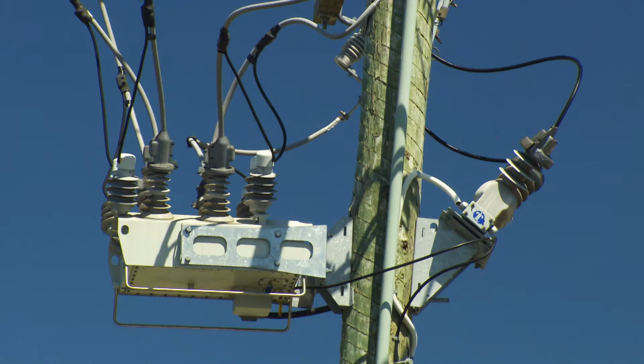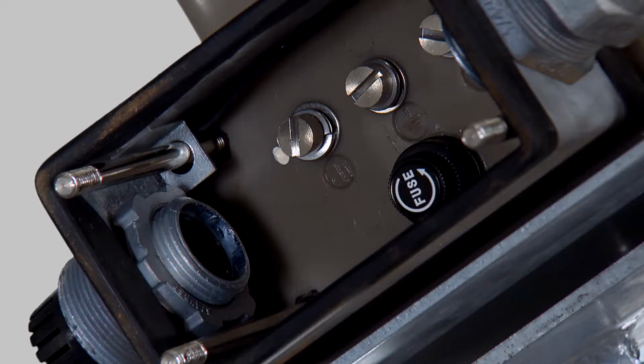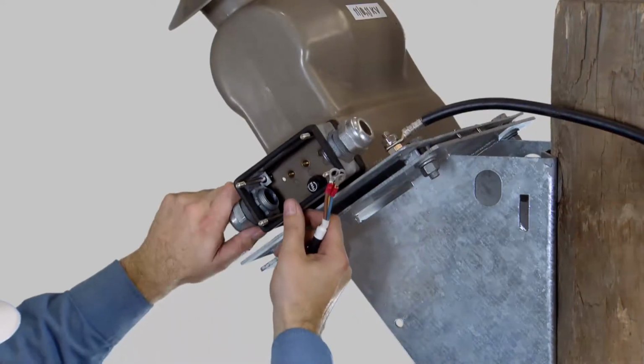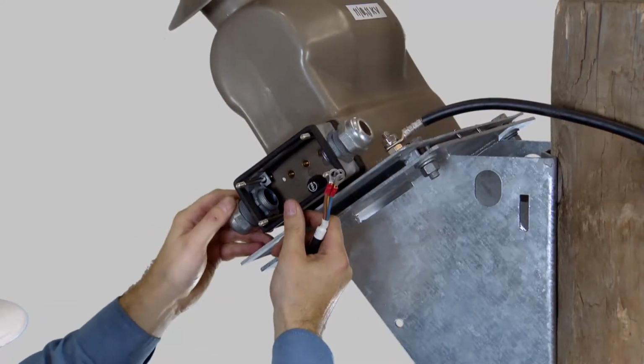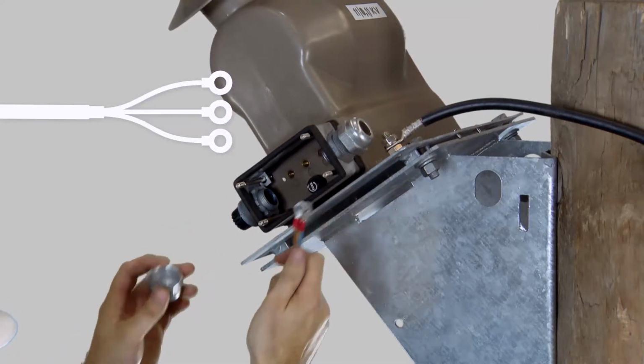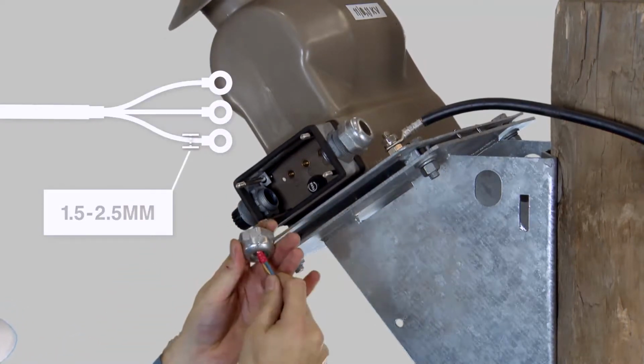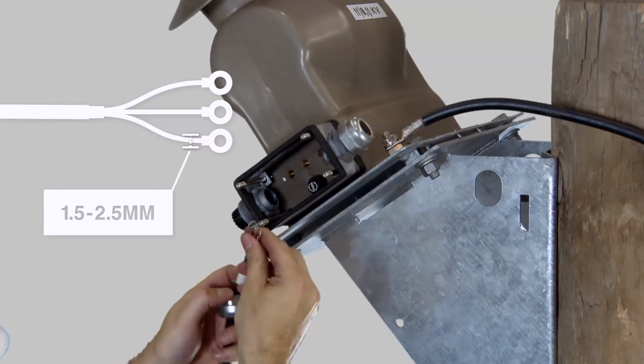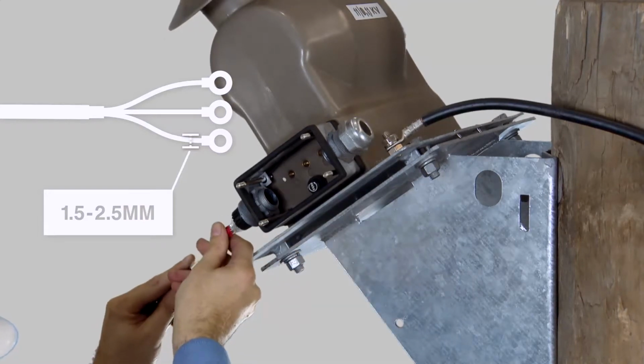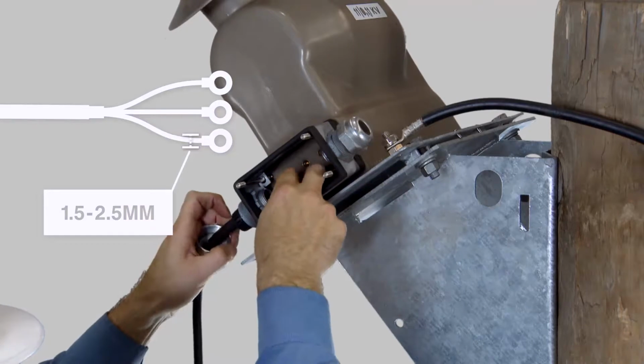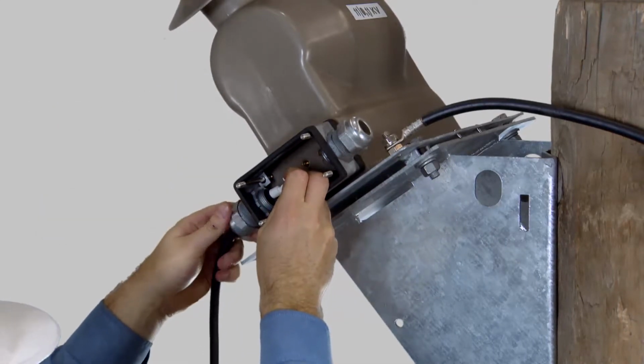NOJA Power supplied VTs are fitted with a 2 ampere fuse in the secondary wiring. This prevents overheating of the secondary side if a short circuit occurs in the wiring down to the RC10. The secondary wiring from VT to RC10 should be between 1.5 and 2.5 mm square of double insulated wire. Thread the cables through the gland and secure so it's weatherproof.